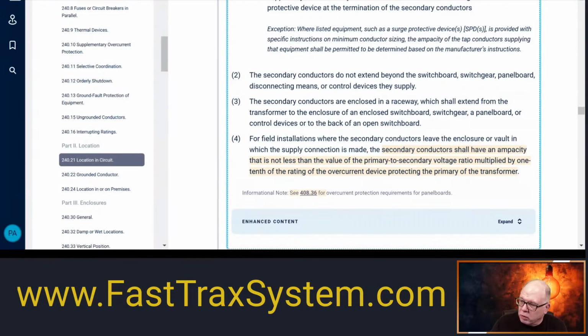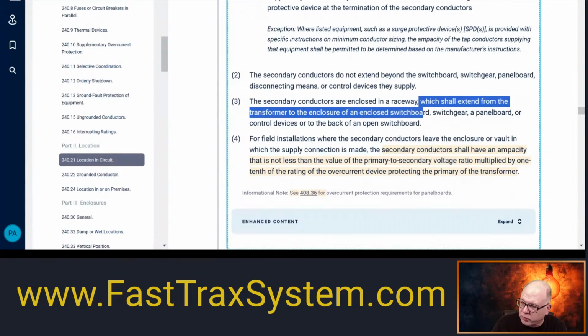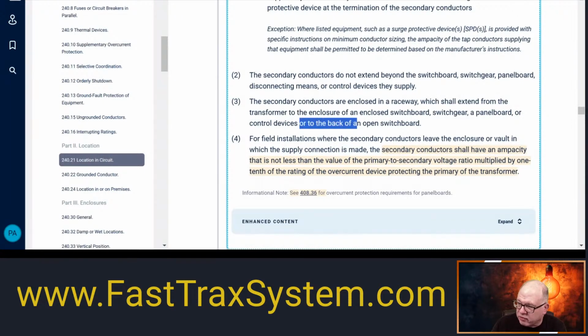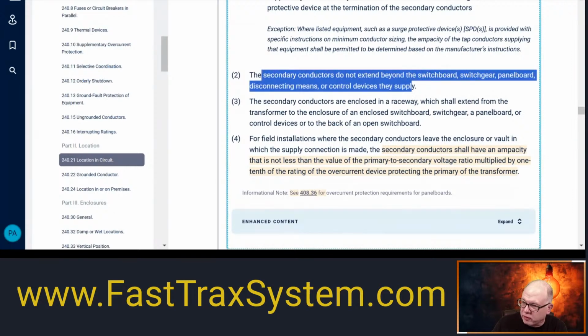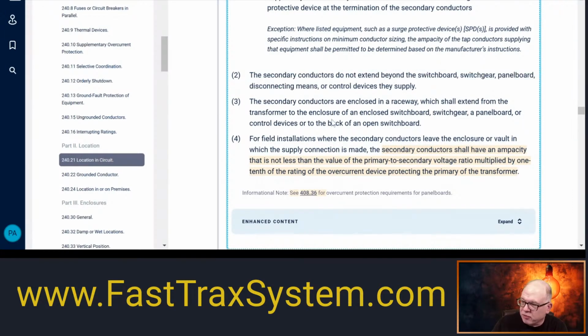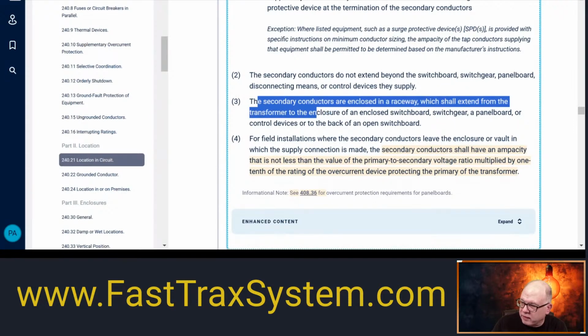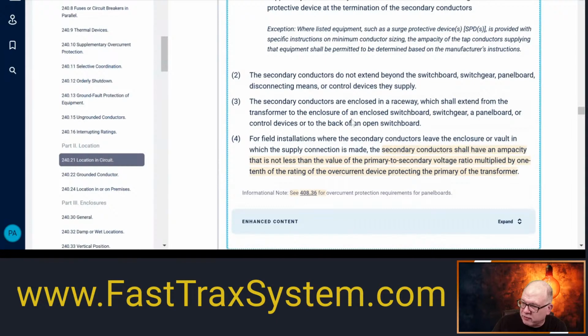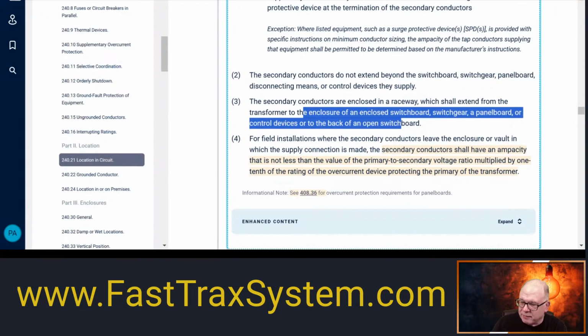Okay, now, the secondary conductors are enclosed in a raceway which shall extend from the transformer to the enclosure of the enclosed switchboard, switchgear, panel board. Again, remember, panel board is the guts inside of the enclosure, or control device, or to the back of an open switchboard. Okay? So into that. Now, what's interesting with these here, it says the secondary don't extend beyond the switchboard, switchgear, panel board, disconnecting means, that type of thing. It almost feels like here it says the secondary are enclosed in a raceway which shall extend from the transformer to the enclosure of the enclosed switchboard, switchgear, panel board, or control devices, or to the back of a. It seems like I would like to have said into the back of a disconnecting means as well. It would have been nice because of this wording up here.